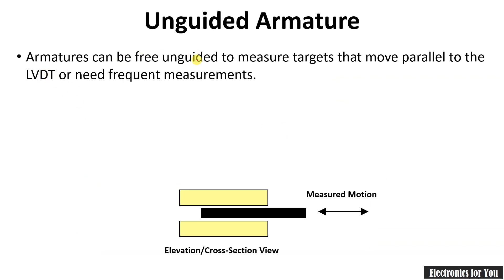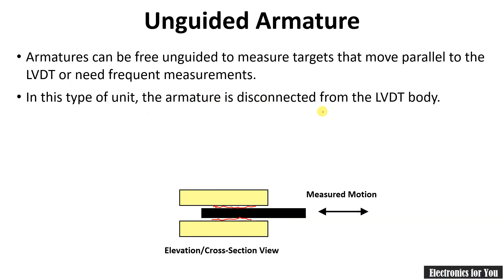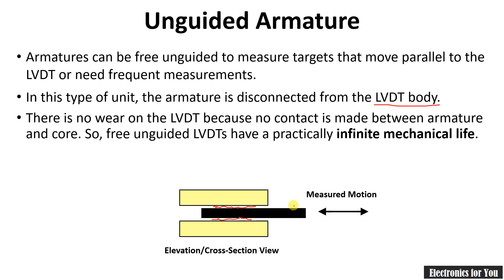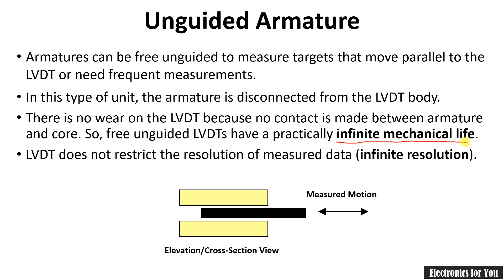The armature can be used to measure targets that move parallel to the LVDT. In this type, the armature can be disconnected from the LVDT body. Since there is no contact of the core with the winding or remaining body parts, there is no wear and tear, giving it infinite mechanical life. It also does not restrict resolution, so it has infinite resolution.